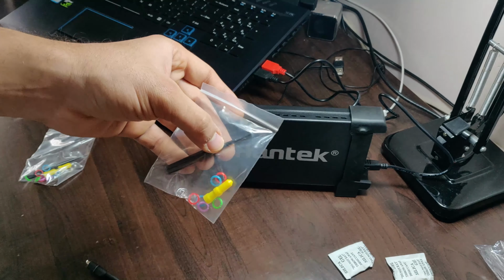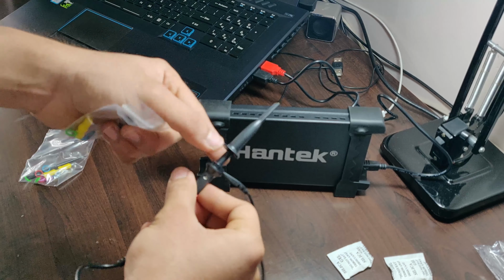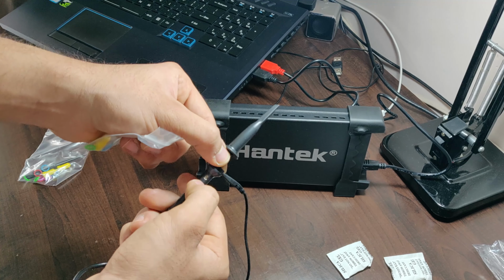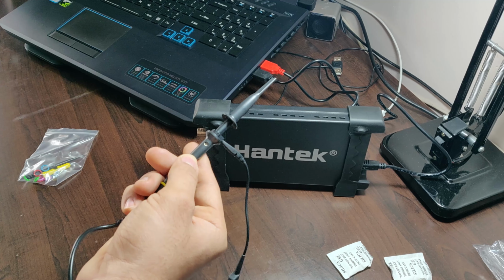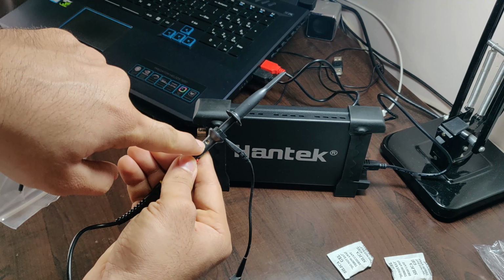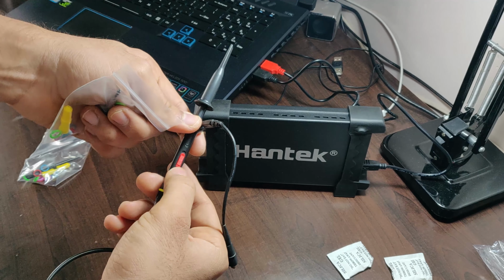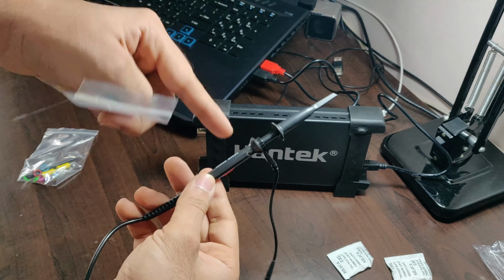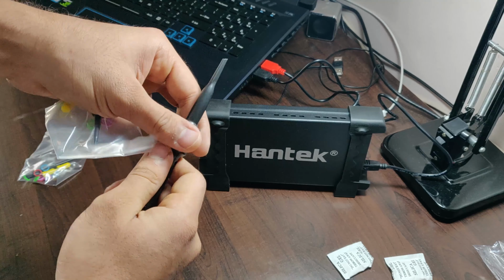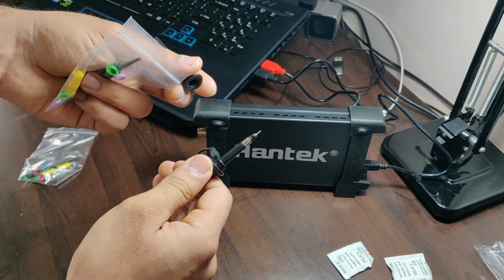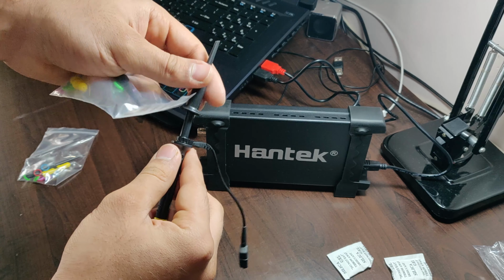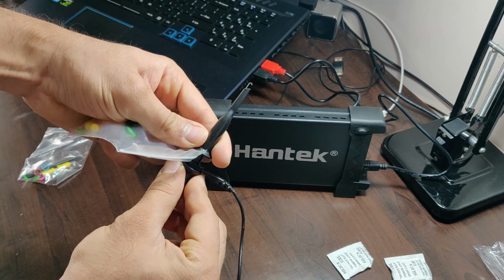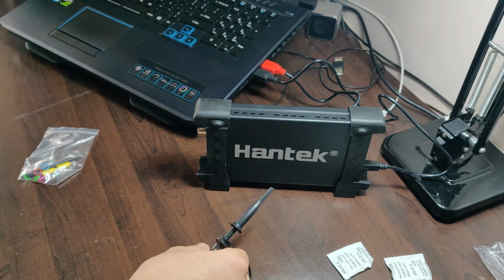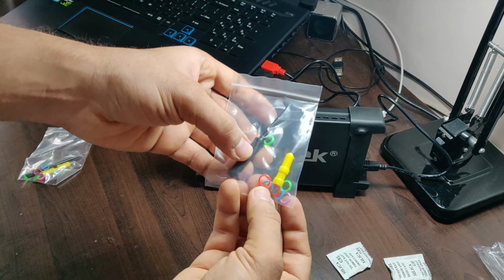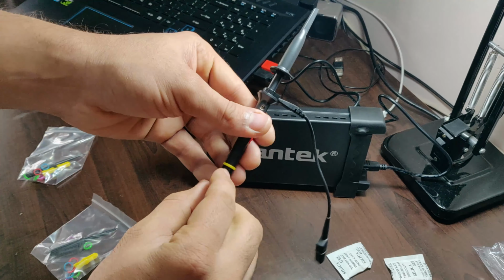So coming into the accessories, what we got with the probe, here you have a screwdriver which is used to calibrate the probe. Usually we have a square wave reference, the signal generator on the oscilloscopes, which is used to actually calibrate the probes. So during the calibration you have to set the attenuation ratio to 10x. As you can see, we have a slide switch as I told you before, and you also have a hook tip which can be detached, and you can place some other kind of sleeves which is required for you. In my case, I will start using the hook tip initially, and also you get the marker rings which is used to, you can change those marker rings on the probes for identification.